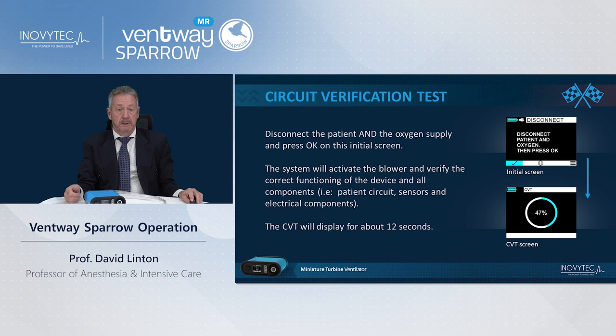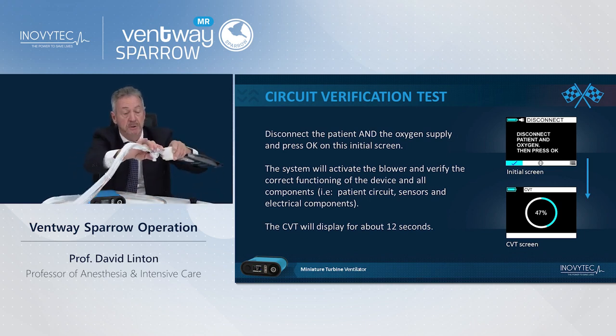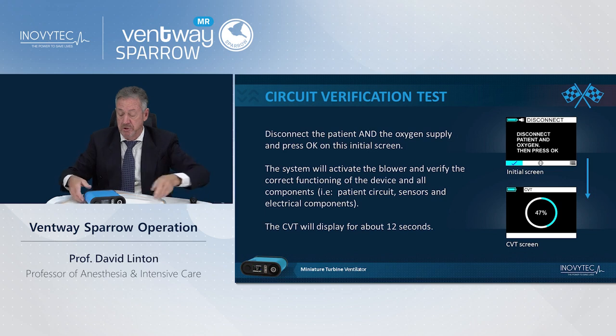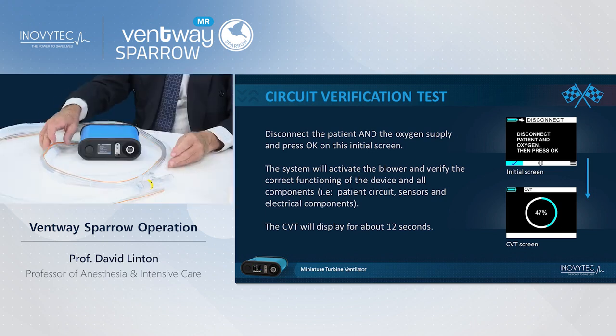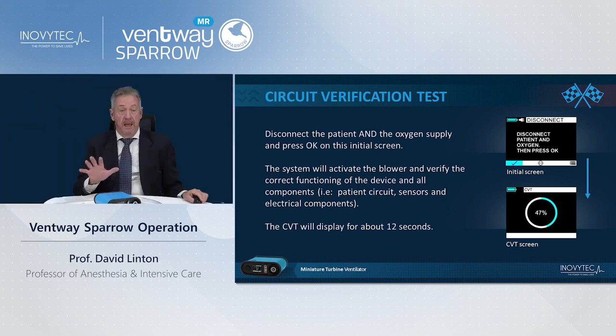If you look at the PowerPoint presentation, you will see what will appear on the screen. It says disconnect the patient and the oxygen, so you have to disconnect the patient and the filter and the oxygen and everything else, and you only have the ventilator circuit in place. The machine will now do a circuit verification test to see that everything is in the right place and the circuit is working properly. It will do it in 12 seconds, and you will watch it being done, and then you'll be able to move to the following position.